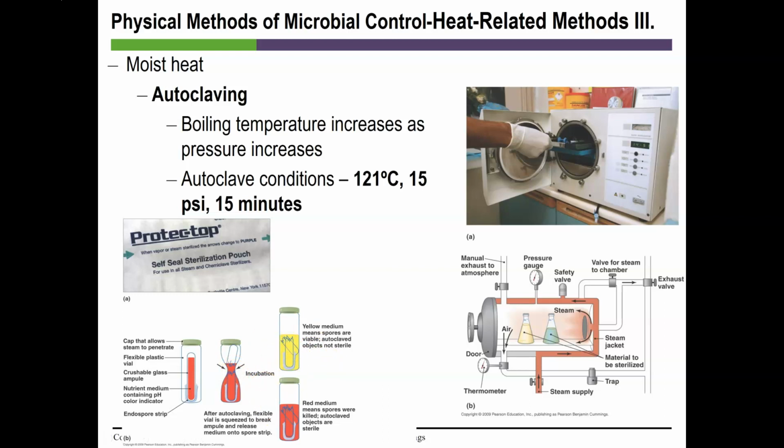You can see on the bottom that this unchanged vial means that you killed all the spores because the color did not change in the medium. The one that did not go through the autoclave grew, indicating that the test vials are still working as you expected, and you can believe the test vial result. This is how we test our autoclaves to verify their function each semester.